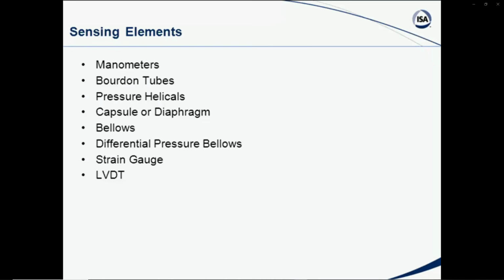Well, we don't have time in this particular treatise here that we're dealing with on this seminar, but here's a list of some of the typical sensing elements. For instance, a manometer. A lot of you are familiar with a U-tube manometer that's filled with some liquid. Could be water or some other, but as long as we know the specific gravity and apply pressure to one side of the U-tube, and we reference the atmosphere or another unknown pressure on the other side of the U-tube, the liquid will move in the column and give us how much pressure has been applied to it.